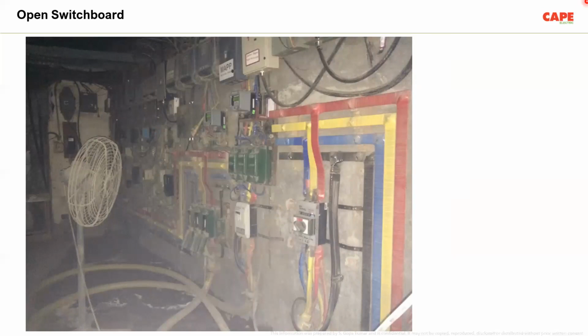I was told that this is an open switchboard. It is inside a room, and the room has a door and a lock. So it is in a locked condition. But unfortunately, the lock was with the security man, and he was opening it up and going inside this room as and when he required. This is like a meter room, with a lot of fans, because the bus bars and the devices are hot, getting heated up. In order to cool down, fans are used.